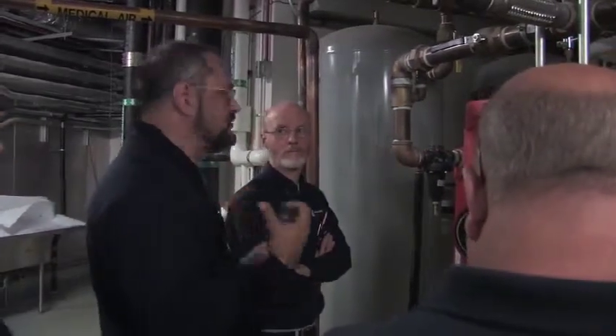The other thing to remember is these dryers are sized, this system's rated for NFPA. So the system rating is the output of 2 of these compressors, not 3. Because one compressor is always going to be a redundant backup. So the dryers are sized to each handle the full output of 2 compressors running full bore. So the point is, if you're not using that much, if you've only got one compressor running and it's only running half the time, life should last.